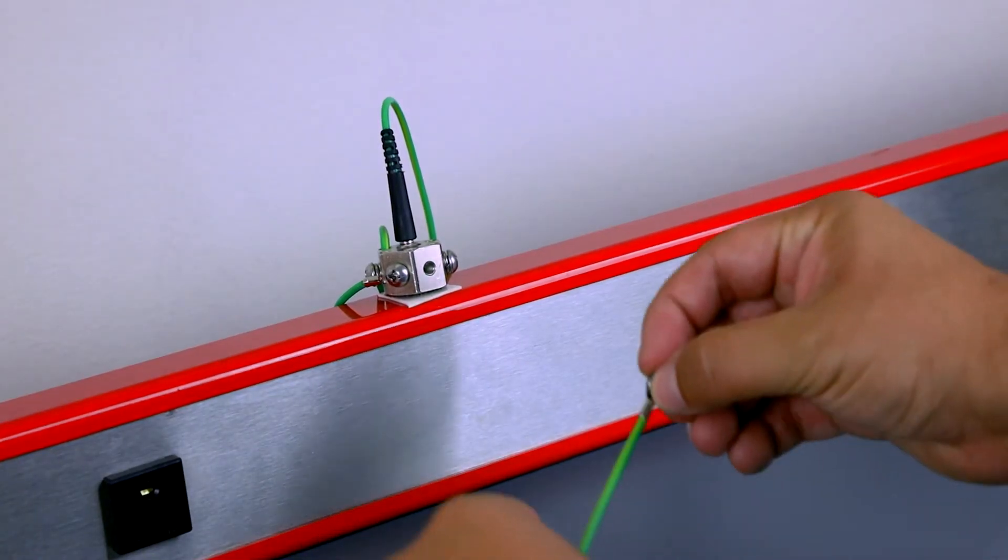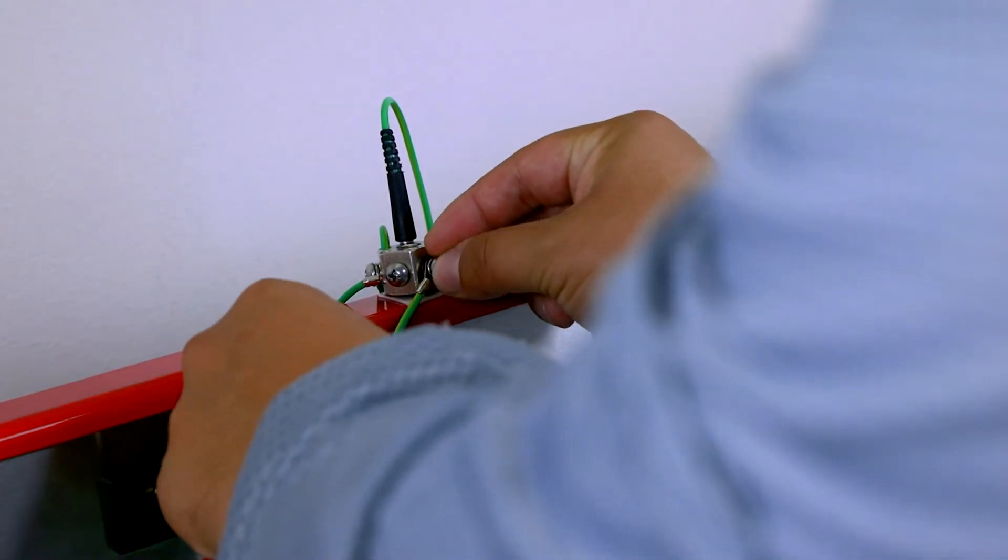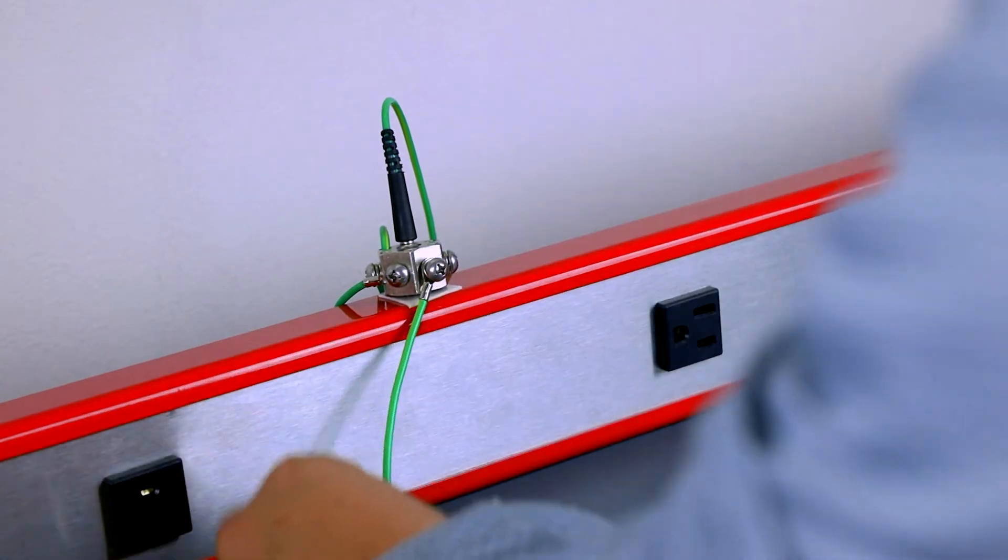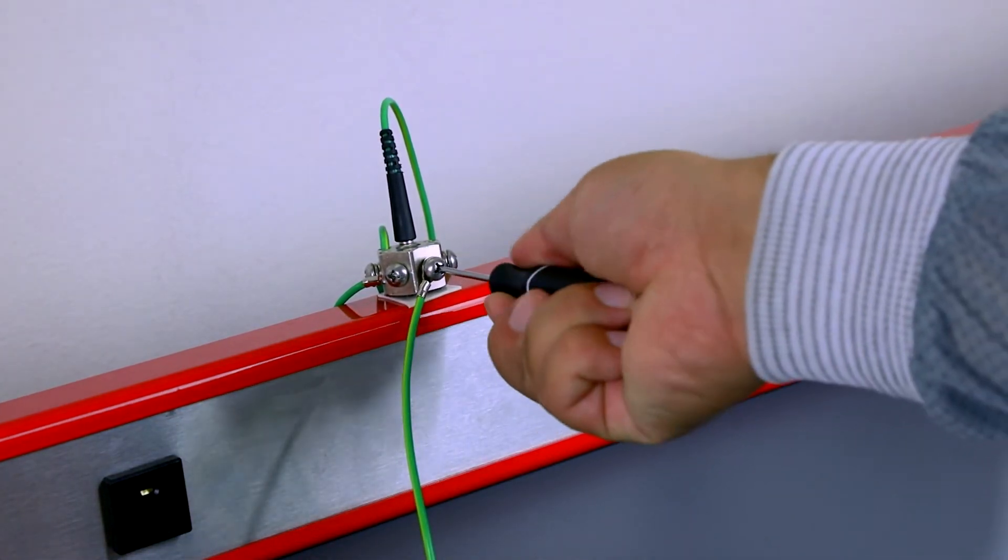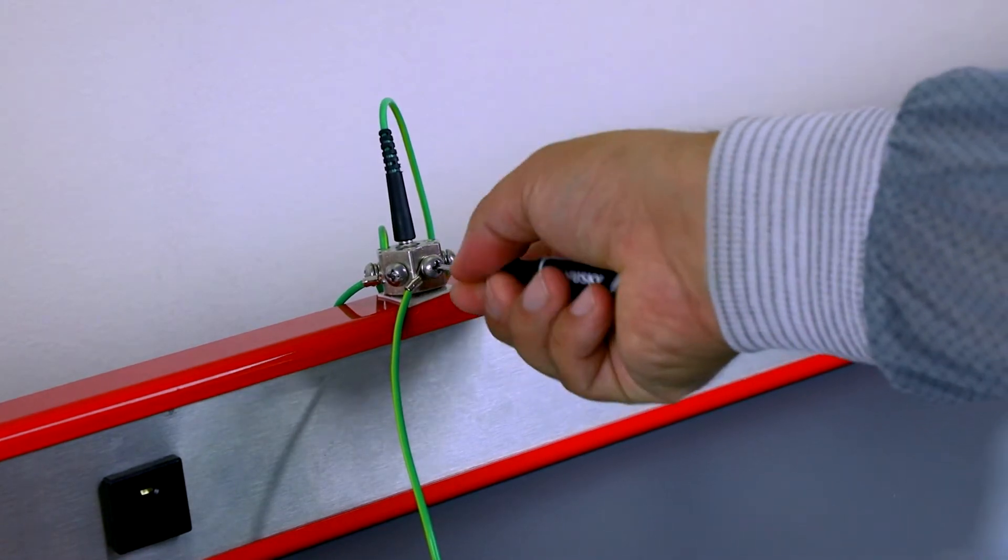Begin by connecting the green monitor ground wire to a ground facility outlet or if connected to a workbench, an installed grounding hub that is connected to the facility ground. This is done via the ring terminal end of the cord.